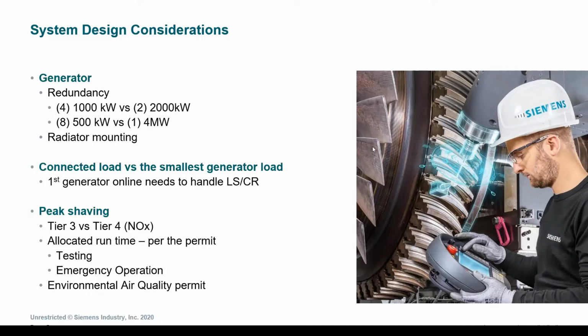Additionally, although the ATSs and parallel switchgear have the ability for many different functions, such as peak shaving, it's important to remember the generators have tier ratings, which are determined largely by their NOx emission levels. It's also worth mentioning that it varies county to county, but many of the counties have permits that determine their operation time. And of course, when a facility loses power and the generators are on emergency mode due to utility power loss, this does not count as hours on their permit, as long as it's documented.